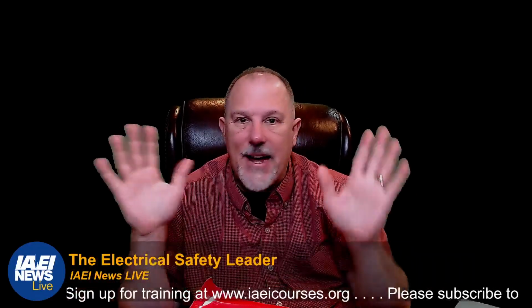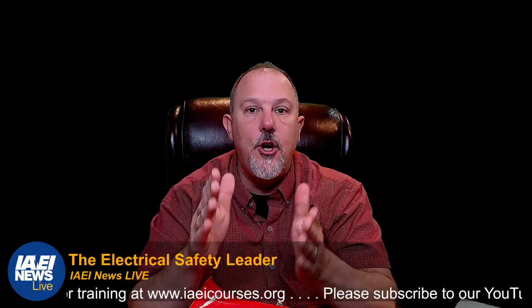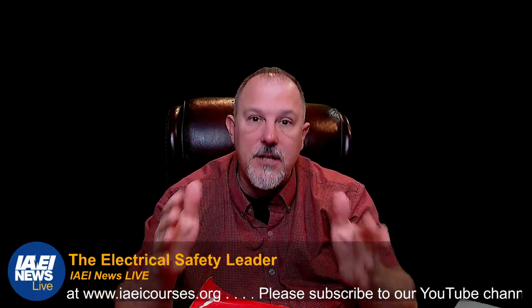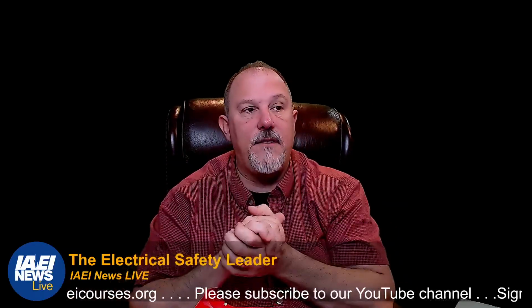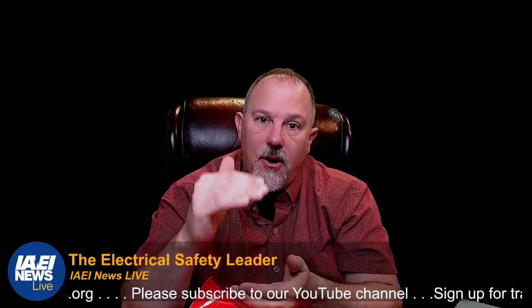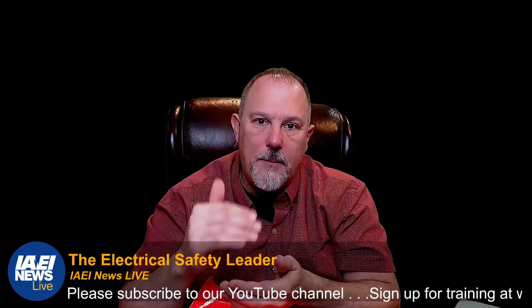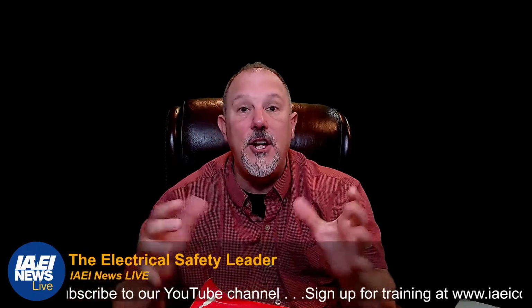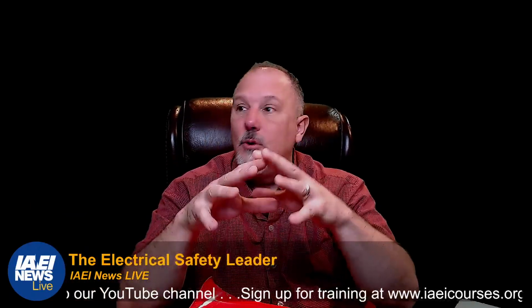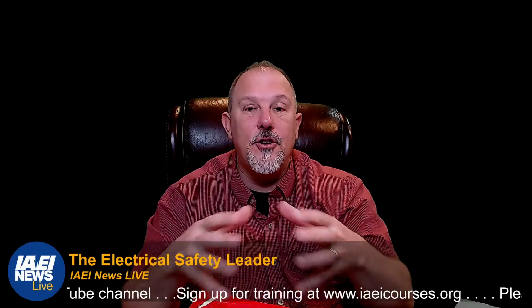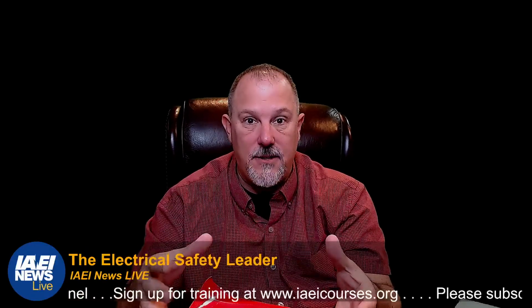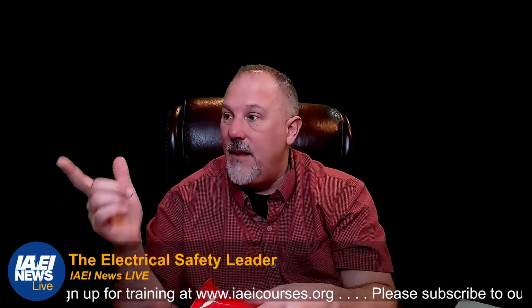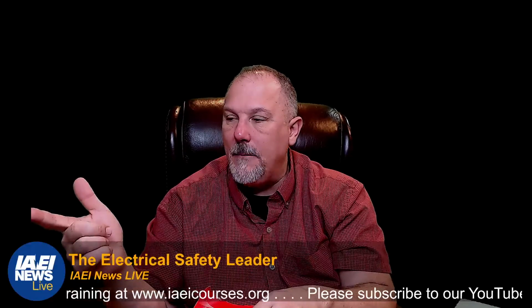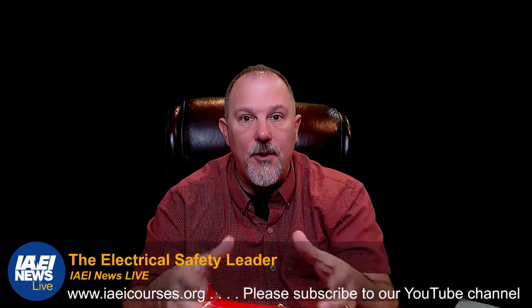You're going to vacuum all of that stuff out, clean the insulation and the insulators. You're going to verify all of the breakers have the right ratings, that they're the right breakers based on the documentation. You'll do your visual inspections, your cleaning, your mechanical inspection of all the physical mechanical stuff, and then if you have to do any electrical tests, you'll do all of those.